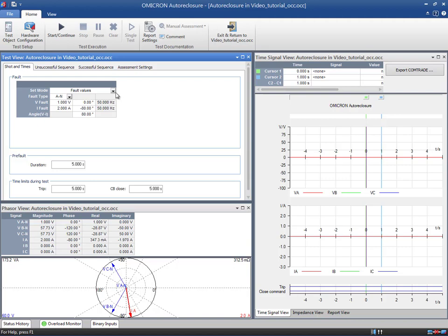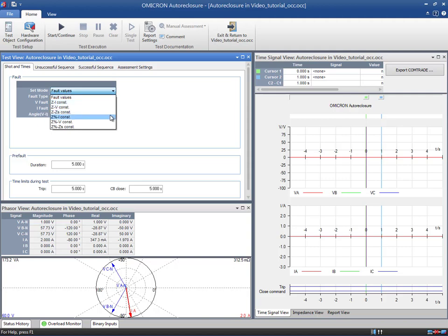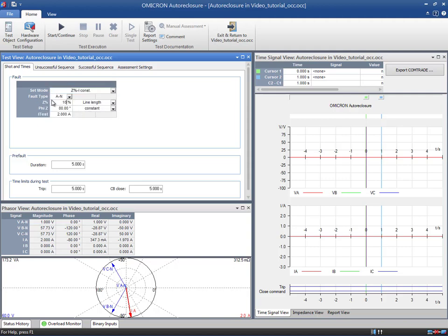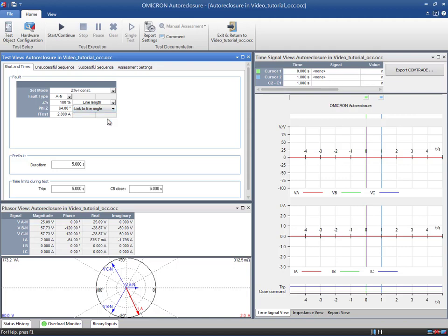Therefore, we choose the Impedance Set mode with Constant Current so we can locate the fault at 100% of the line impedance. We set the fault angle to the line impedance angle, that is, 64 degrees. We can also use the Link to Line Angle option. If you change the line angle in the real block distance of the test object, the fault angle will adapt automatically.